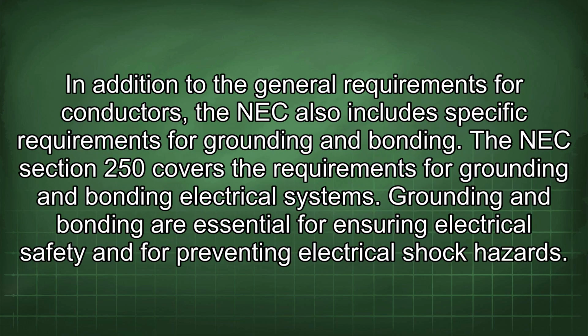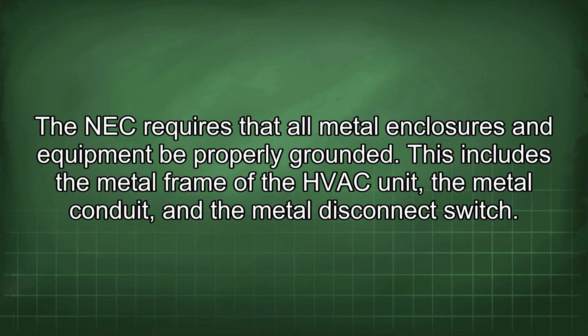In addition to the general requirements for conductors, the NEC also includes specific requirements for grounding and bonding. The NEC section 250 covers the requirements for grounding and bonding electrical systems. Grounding and bonding are essential for ensuring electrical safety and for preventing electrical shock hazards. The NEC requires that all metal enclosures and equipment be properly grounded. This includes the metal frame of the HVAC unit, the metal conduit, and the metal disconnect switch.